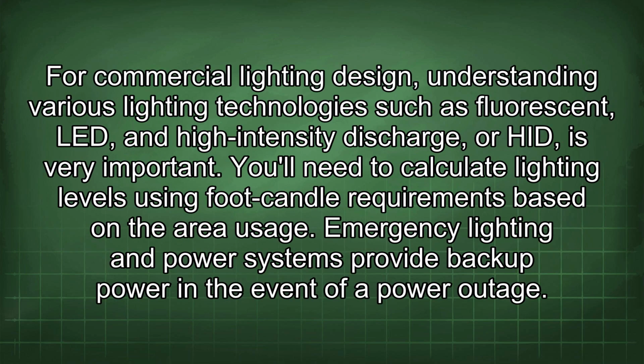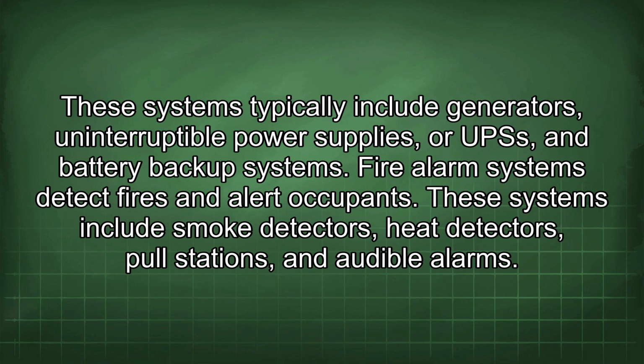For commercial lighting design, understanding various lighting technologies such as fluorescent, LED, and high-intensity discharge, or HID, is very important. You'll need to calculate lighting levels using foot candle requirements based on the area usage. Emergency lighting and power systems provide backup power in the event of a power outage. These systems typically include generators, uninterruptible power supplies, or UPSs, and battery backup systems.